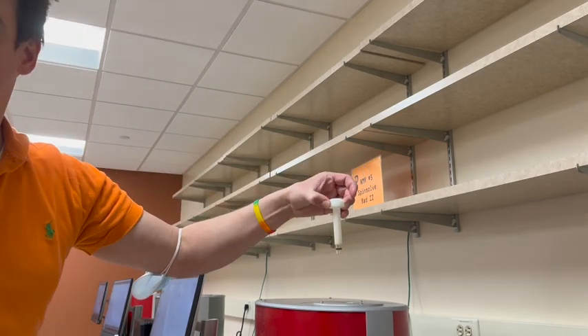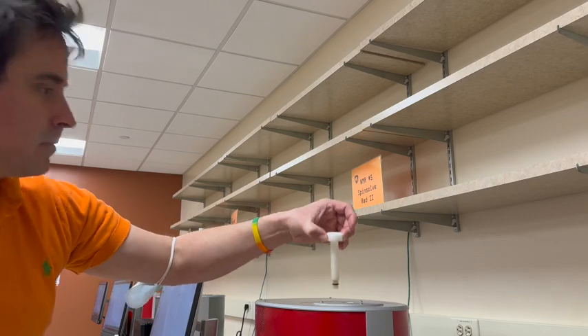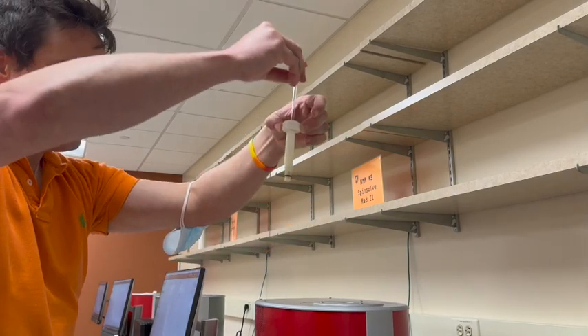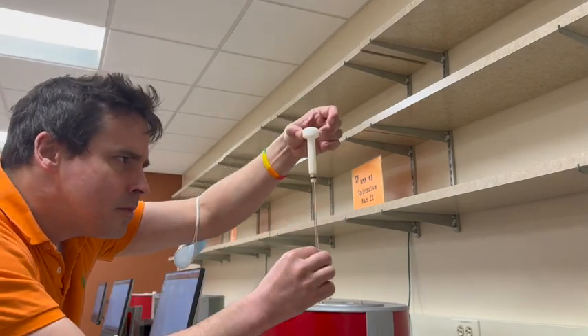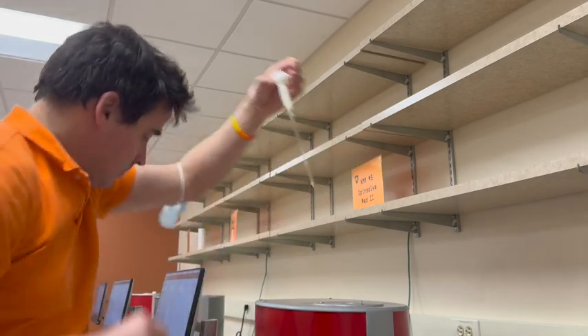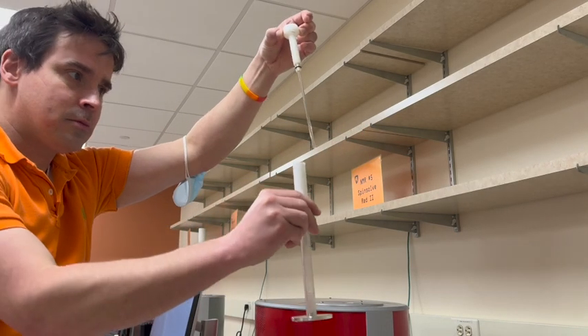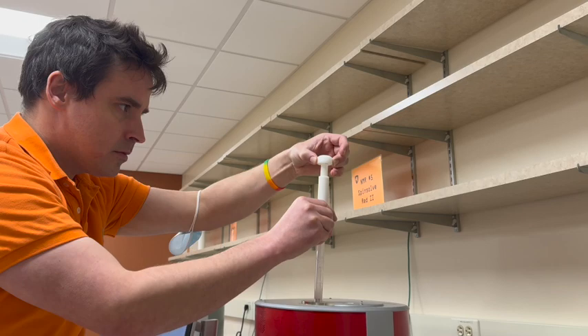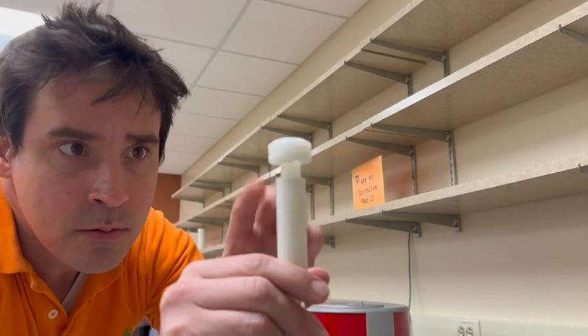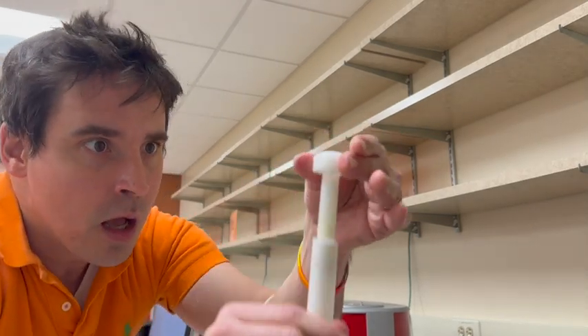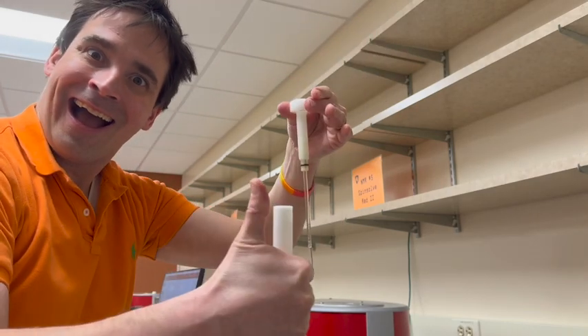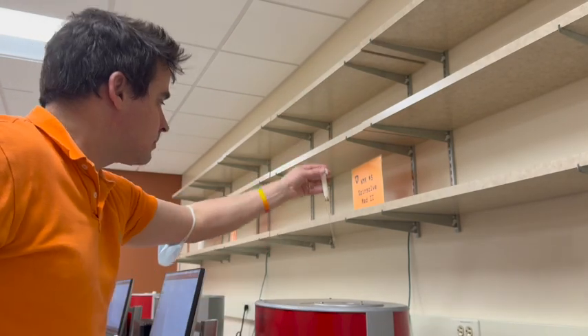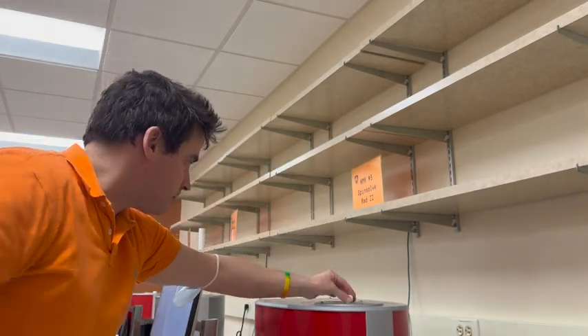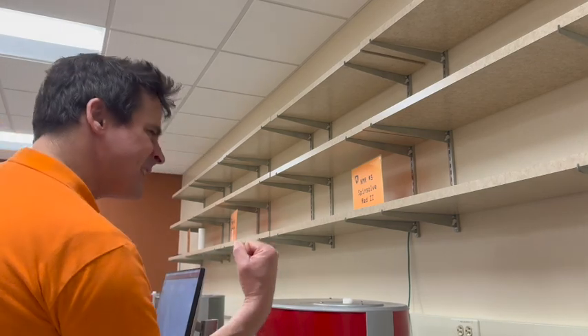Next, take your sample and gently thread it through the top of the spin collar and pull down through the bottom until it basically clicks in place. Next comes the leveling gauge. You will notice that when you place your NMR tube in the leveling gauge, there will be a small gap. Push down to remove the aforementioned gap. Now your sample is at the appropriate height to be nestled in the magnetic field of the NMR. Great success!